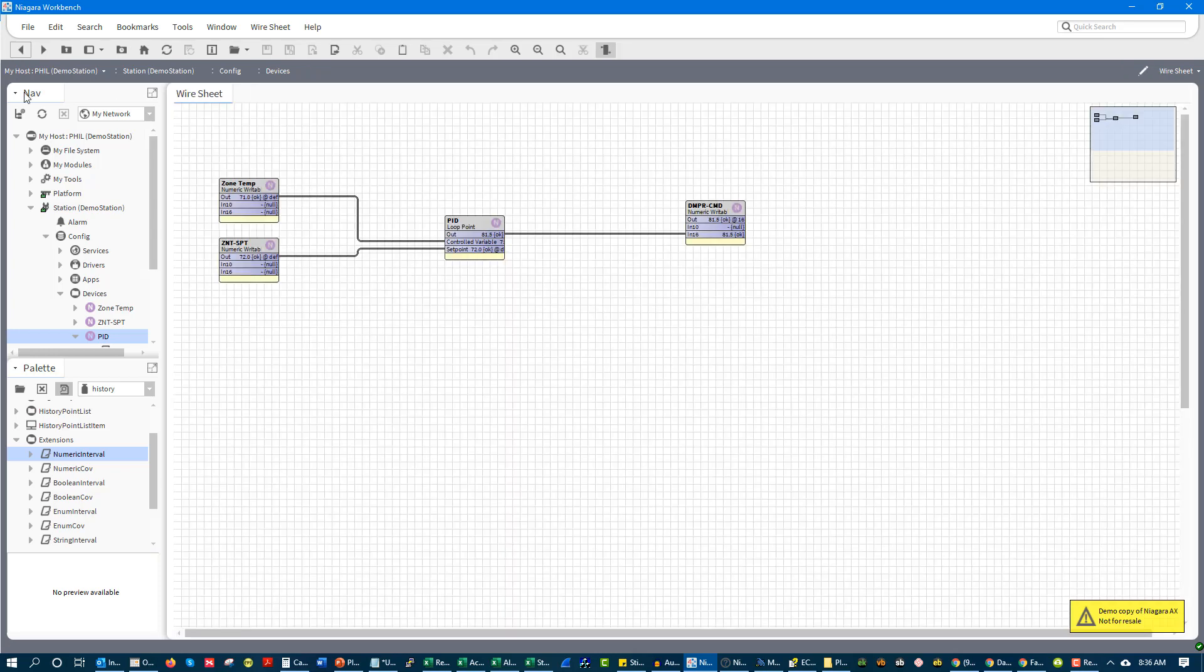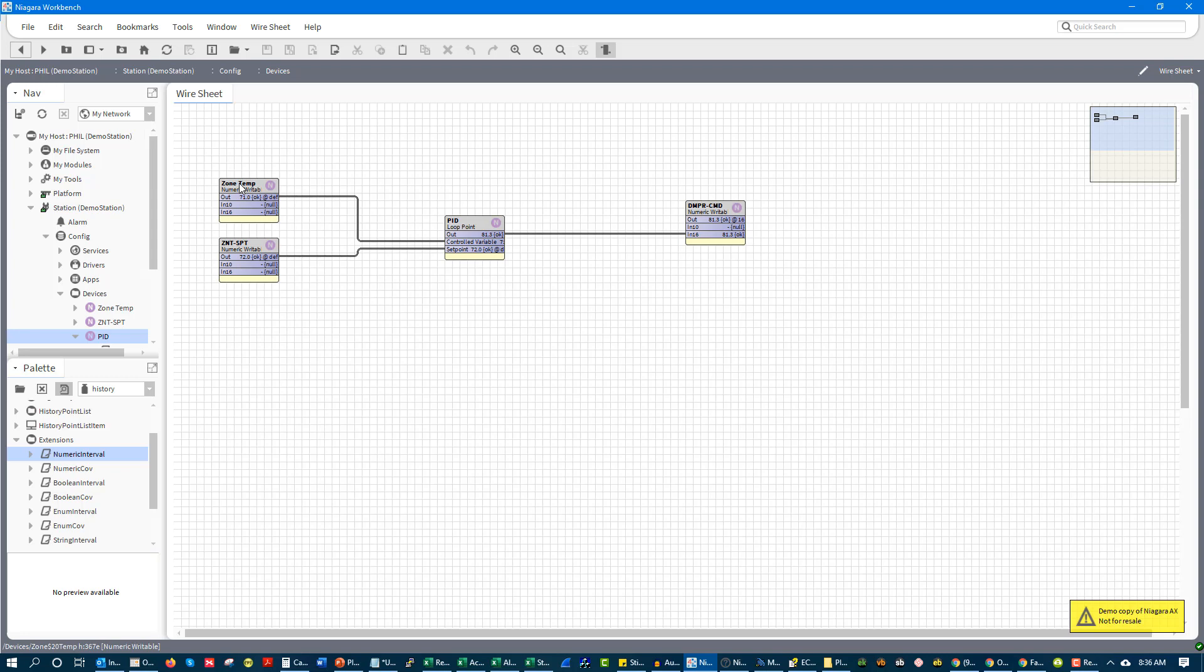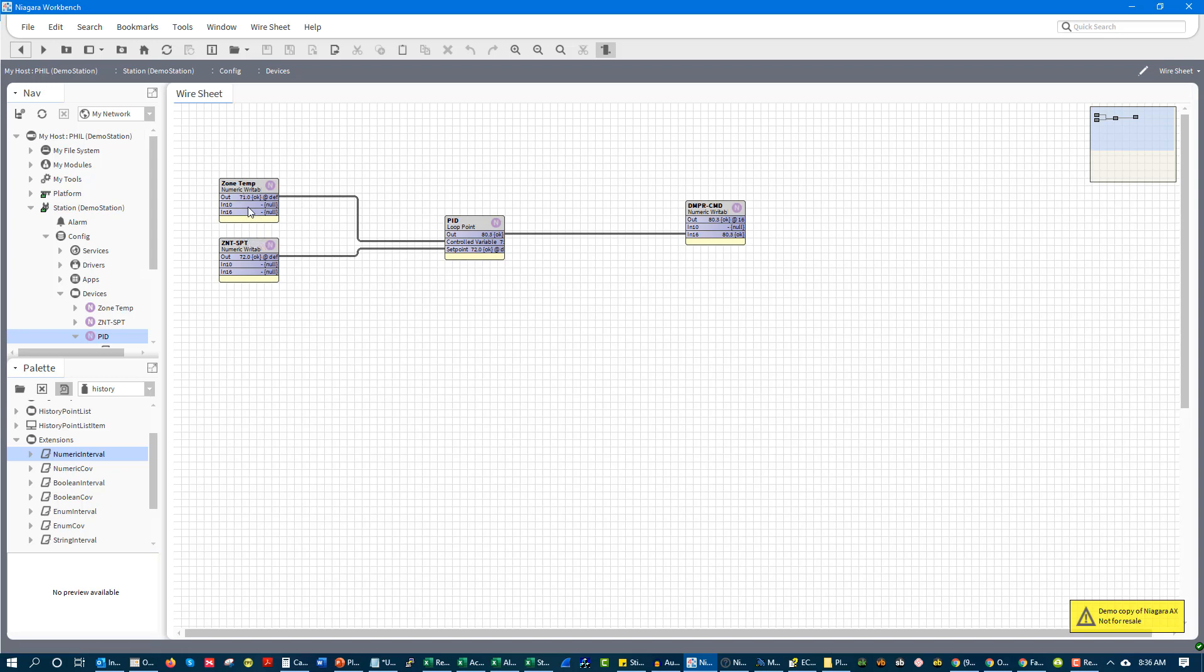So if this were zone temp, we would usually have anywhere from an 8 to a 10 degree sensor span, meaning that while the zone temp sensor can sense from like negative to 300 degrees, what we control to is typically we're controlling maybe 65-75 is our controlled range. Our ideal is to have the zone temp at 72, but it could dip all the way down to 65 when the building's unoccupied, or it could go up to 75. And so we have a 10 degree sensor span.